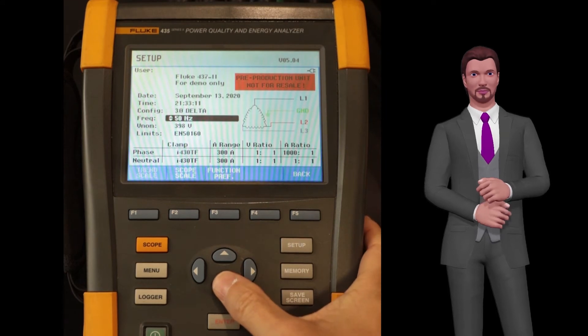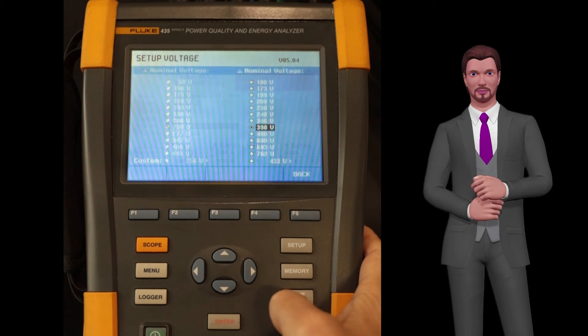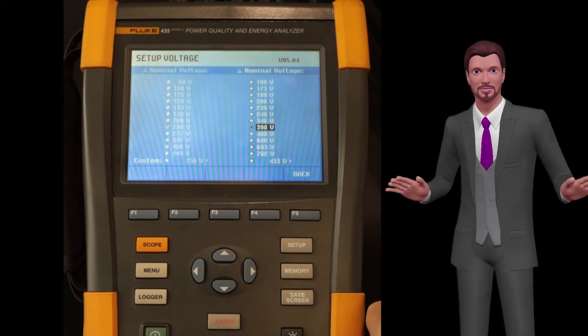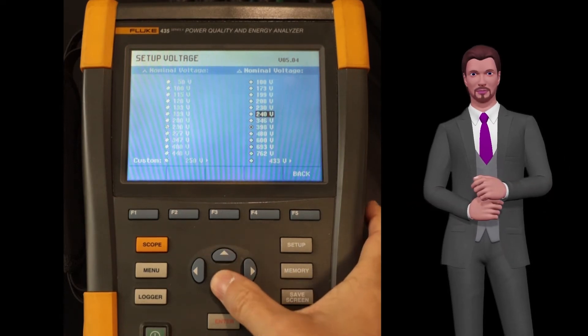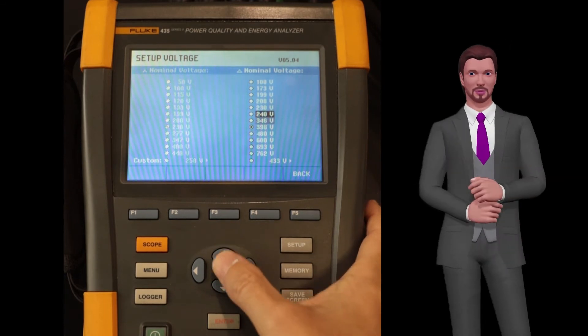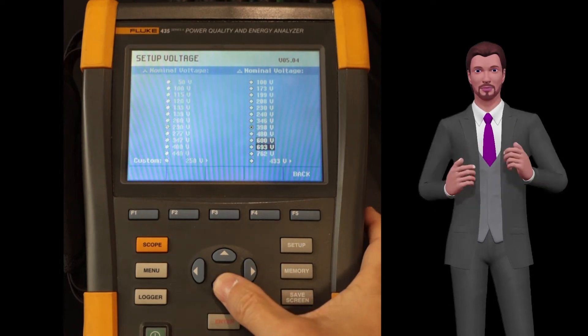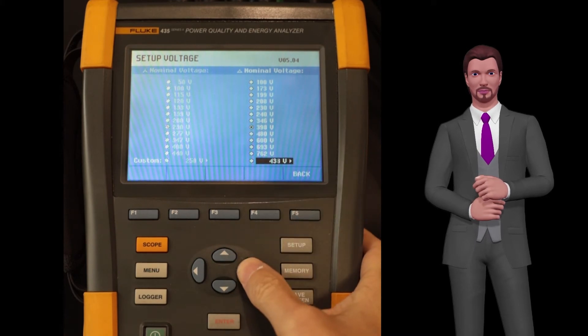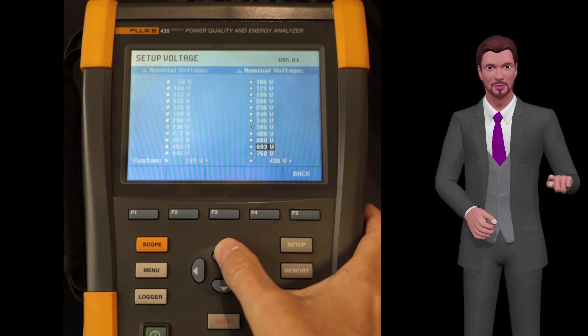Now we go down with the down arrow key to the option VNOM, to set the nominal voltage, and press enter. By default the voltage of 398 volts appears selected in the right column, but we can change it if we wish. Keep in mind that in this case, the value to be selected is the one corresponding to the nominal voltage between phases. If the values that appear do not match the nominal voltage of your network, then you can manually adjust it by moving down to the last position marked custom. In my case I leave it at 398 volts and press the F5 back key.